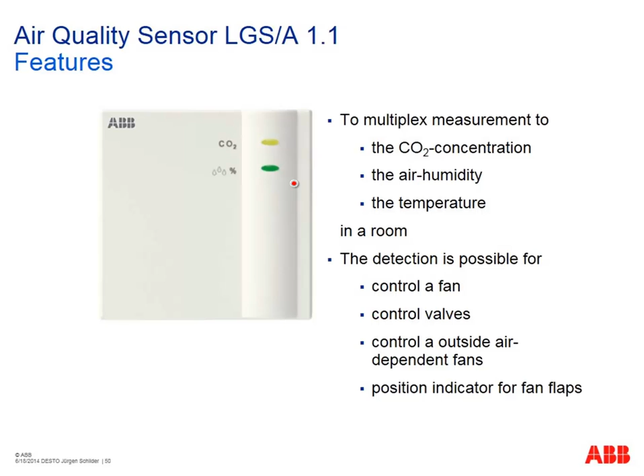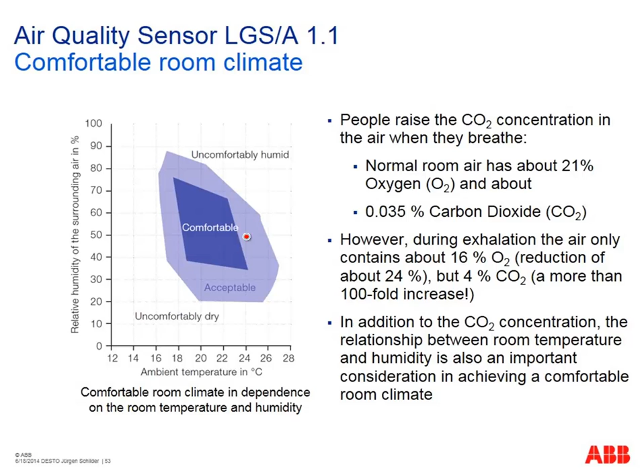And I mentioned already it's not only CO2 concentration, but also humidity and temperature. And this diagram shows you quite well the relation between humidity in the room and temperature, where you still feel comfortable. And you see the dark colored range here, between maybe 18 and 24 degrees is temperature okay, but the relative humidity should not have more than 70%, so between 40 and 70%. And with our solution we can influence this with a room temperature controller, but also with this air quality sensor. And with the right, of course, actuators and also hardware options to do this in a room.